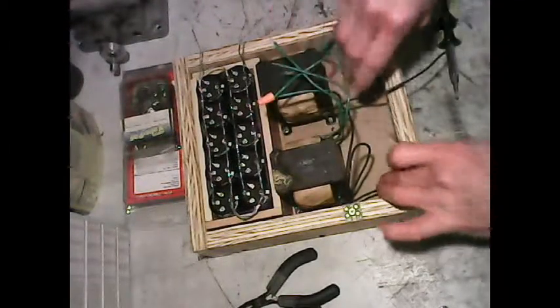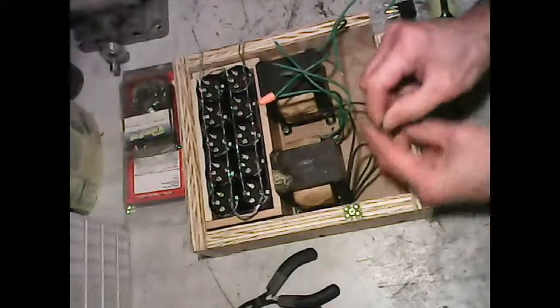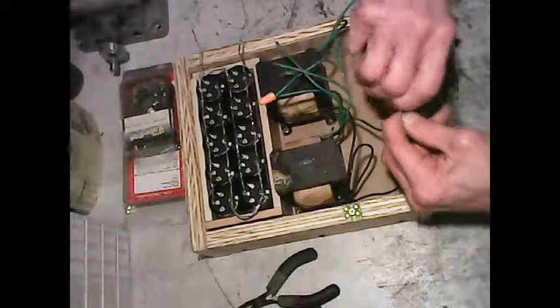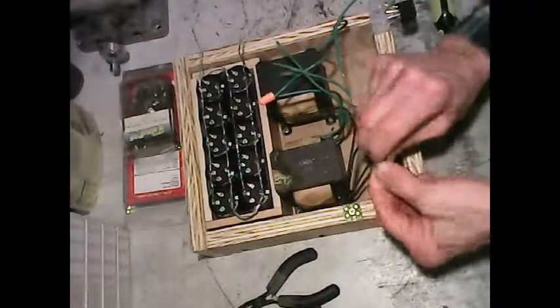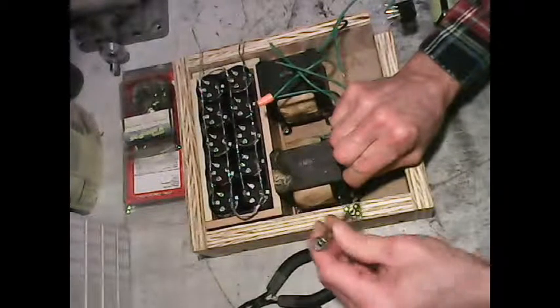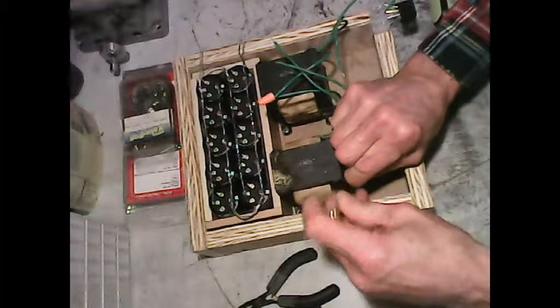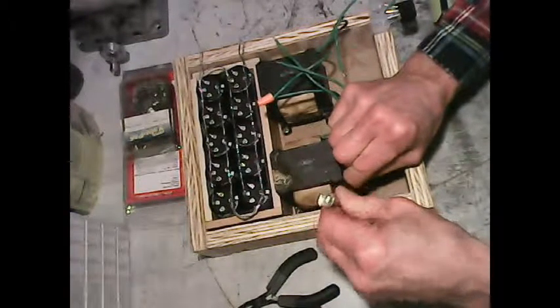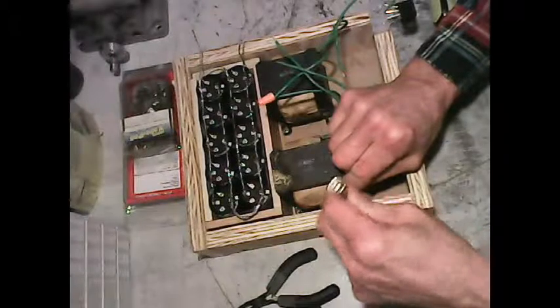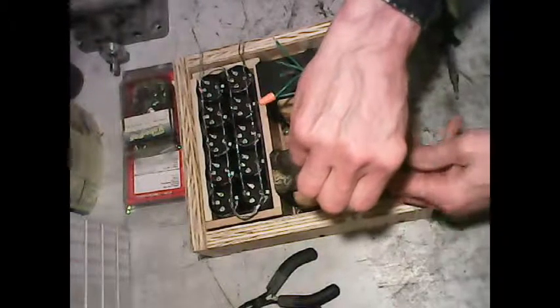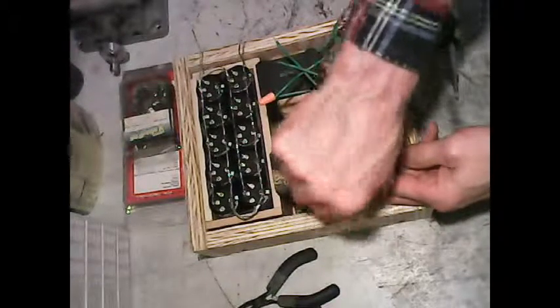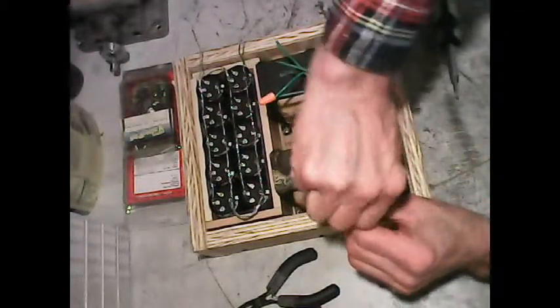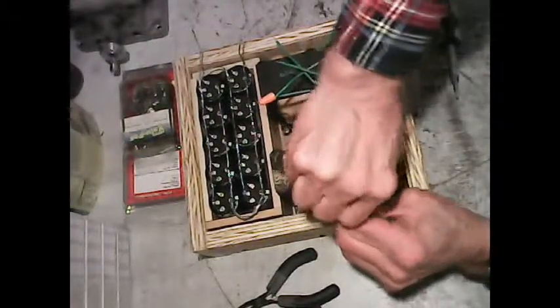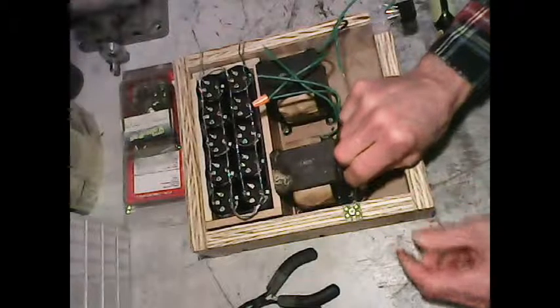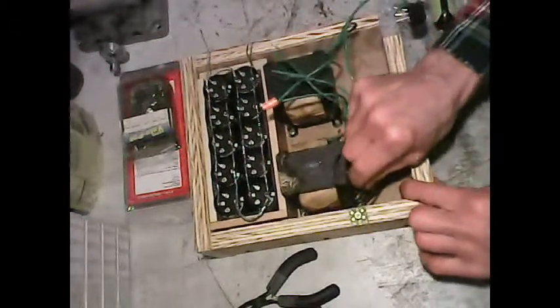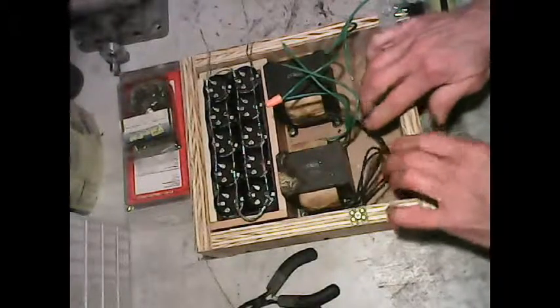And the two bottom wires now - make sure the bottom ones are put together, and that makes sure they're in phase that way, as they need to be. I want power to come to both transformers at the same time. The transformers are only in series on the secondary windings, but they have to be in parallel on the primary windings in order to work properly.